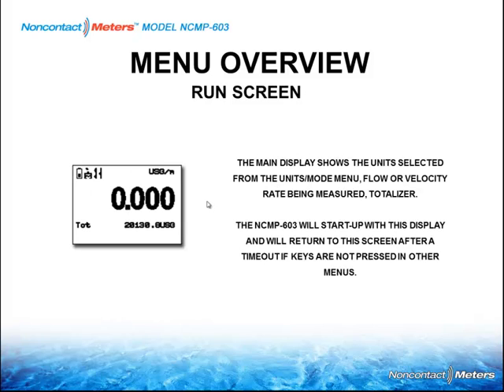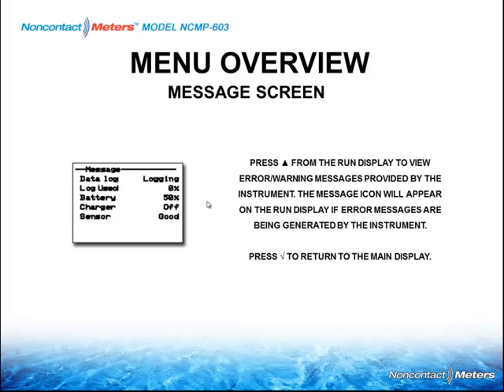It has a very bright run screen. If you don't press a button fast enough, or you get lazy and just leave it on there, it will go back to the run screen itself, and it will basically display the units, the flow rate, velocity, or totalization. On the message screen, this will tell you the status of the data logger, the amount of log used, the amount of battery that you have left, whether the charger's on or off, and the sensor condition.